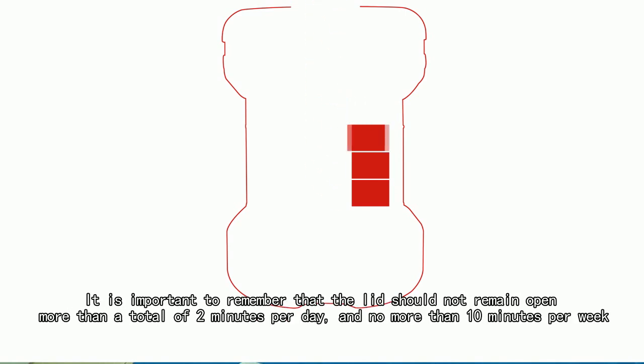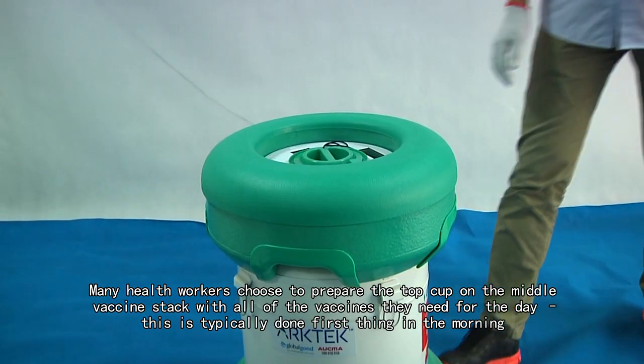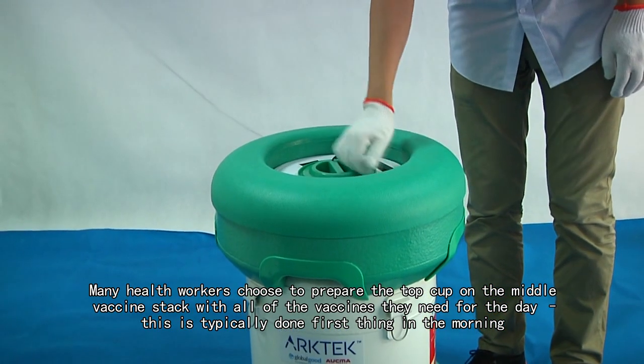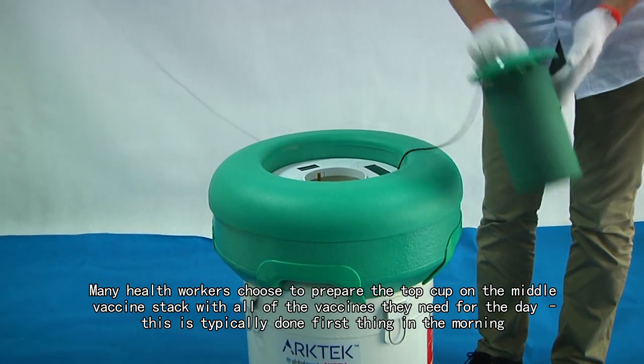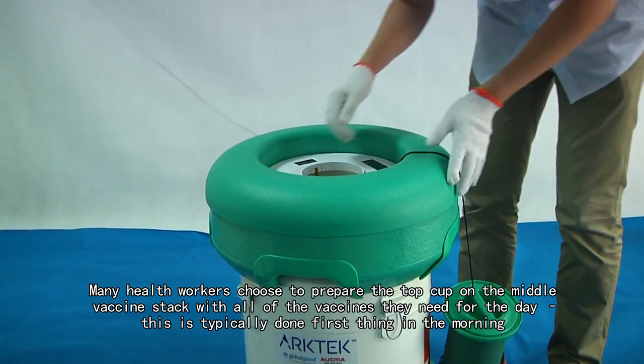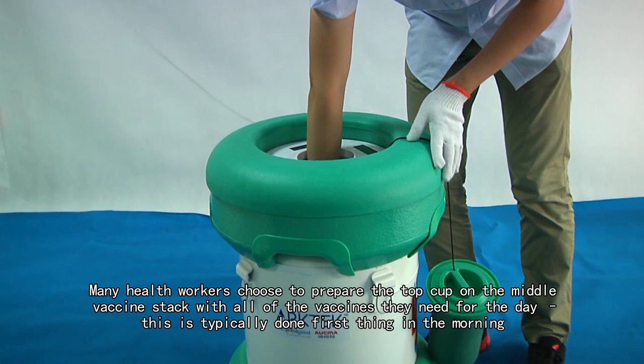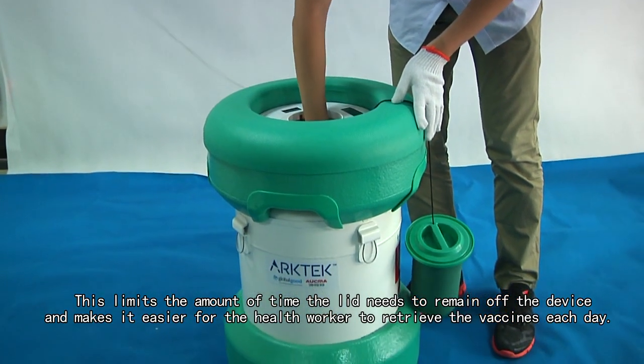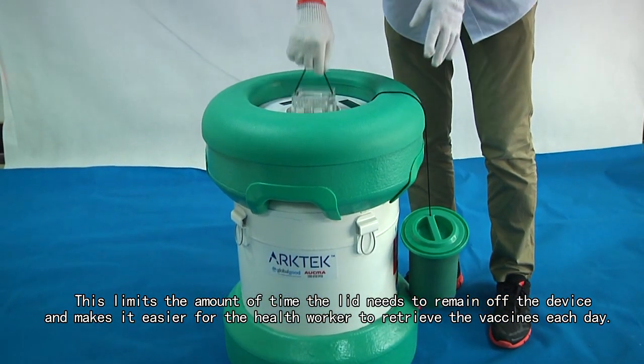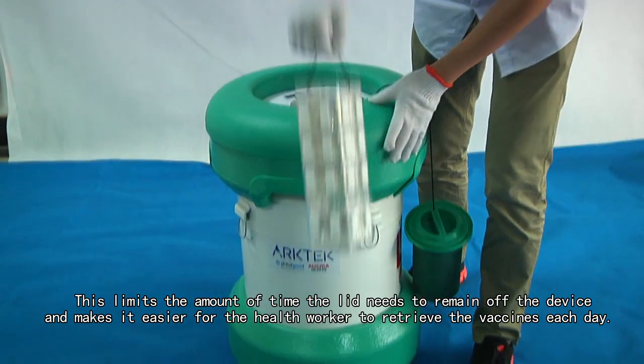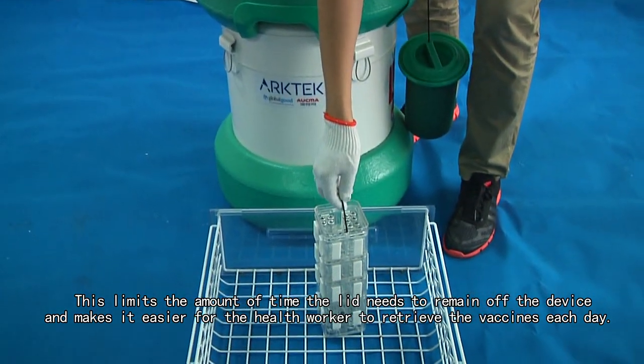It is important to remember that the lid should not remain open more than a total of 2 minutes per day and no more than 10 minutes per week. Many health workers choose to prepare the top cup on the middle vaccine stack with all of the vaccines they need for the day. This is typically done first thing in the morning. This limits the amount of time that the lid needs to remain off the device and makes it easier for the health worker to retrieve the vaccines each day.